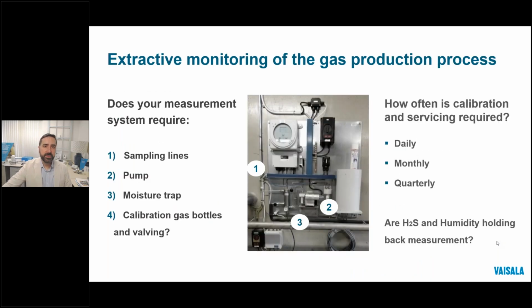A bit more detail about extractive analyzers here, highlighting some of the key components of traditional systems, as these analyzers are not really equipped to measure hot and wet gases. They're going to involve a sample pump, stainless sample lines, moisture traps, and sometimes connected bottles of calibration gas to maintain accuracy. It's quite the assembly to maintain for getting the gas to the sensor bank.